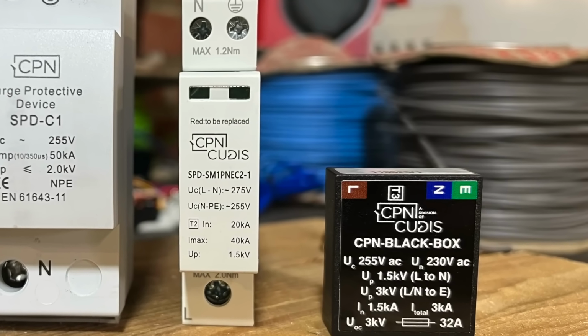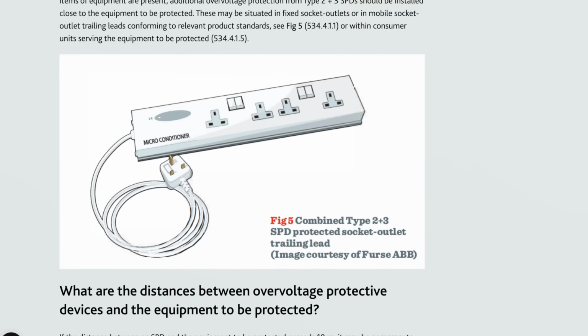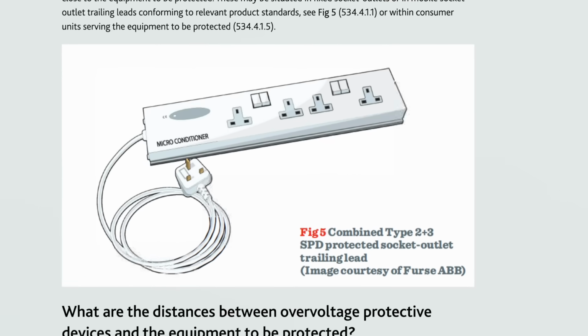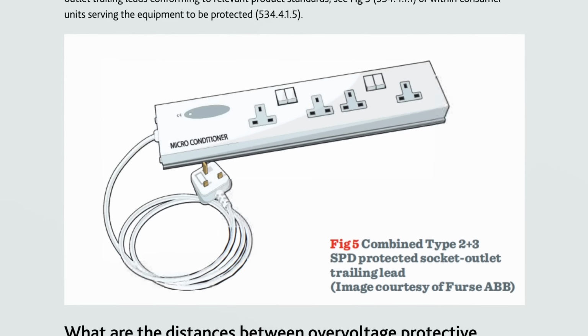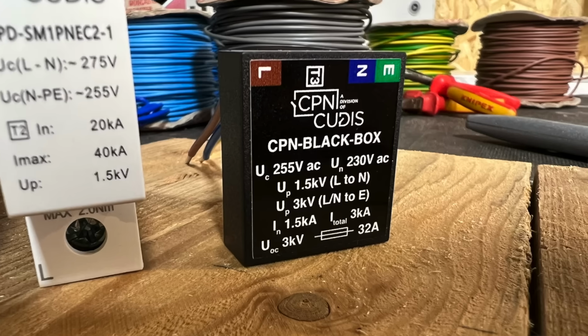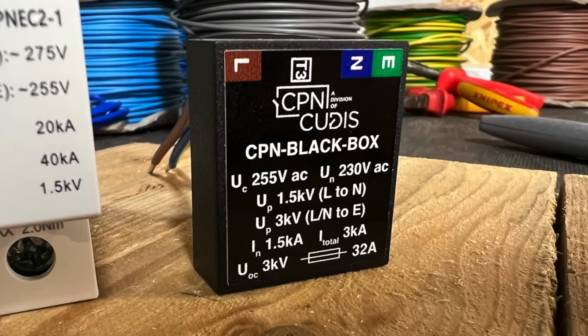These may be situated in fixed socket outlets or in mobile socket outlet trailing leads conforming to standards, or within the consumer unit. If the distance between an SPD and the equipment to be protected exceeds 10 metres, you must install additional SPDs close to that kit.